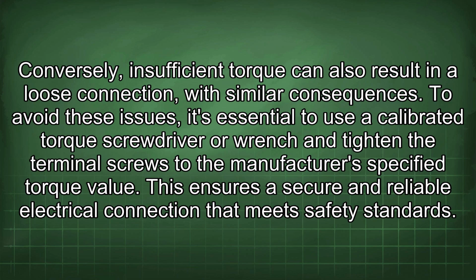To avoid these issues, it's essential to use a calibrated torque screwdriver or wrench and tighten the terminal screws to the manufacturer's specified torque value. This ensures a secure and reliable electrical connection that meets safety standards.